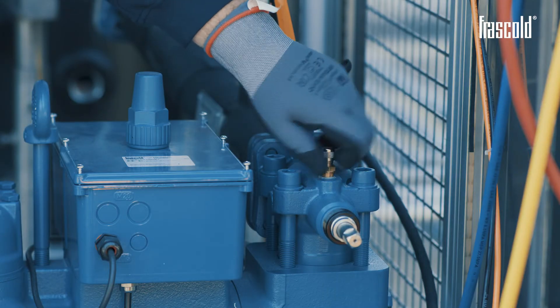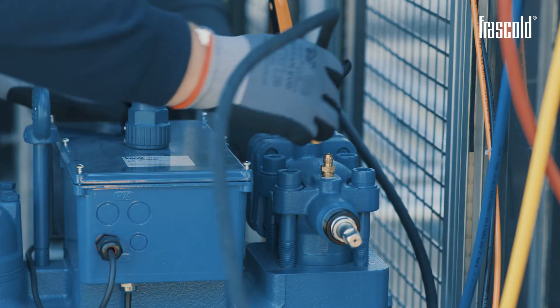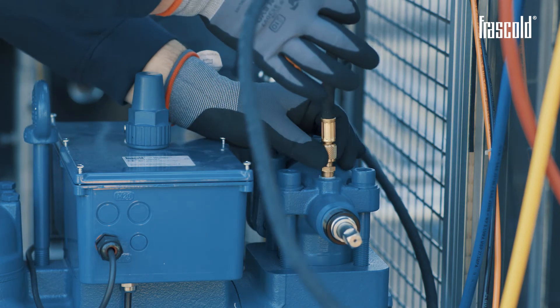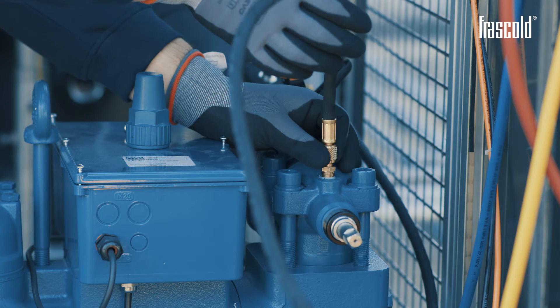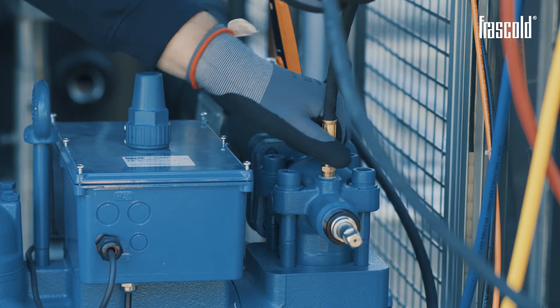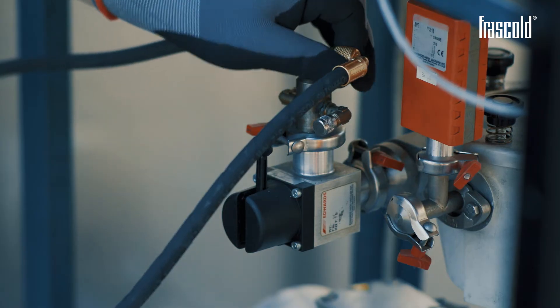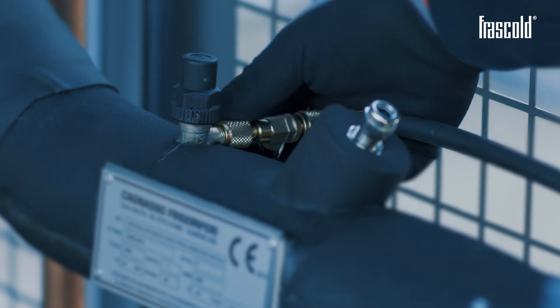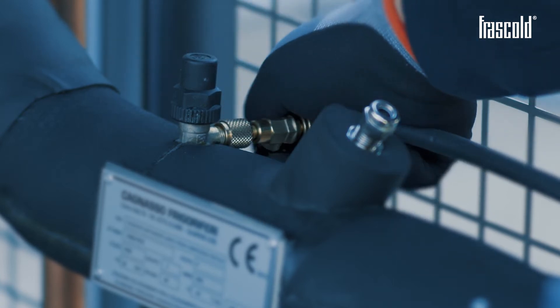Connect all the whip connectors to a single manifold that is connected to a two-stage vacuum pump. Carry out maximum vacuum following the provisions of the EN 378-2 standard. Open the valves connected to the vacuum pump whip connectors previously positioned and turn on the vacuum pump.